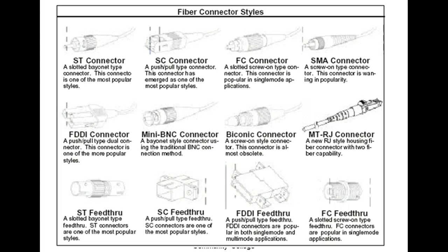These are different types of connectors. Can y'all see these? These are crummy pictures. We have what we call an ST connector. Some people call this a Sierra Tango. And then we have an SC connector. So the connector on the cable that we passed around was an ST connector. This guy here is probably the most predominant connector used in the field, followed by the SC connector.